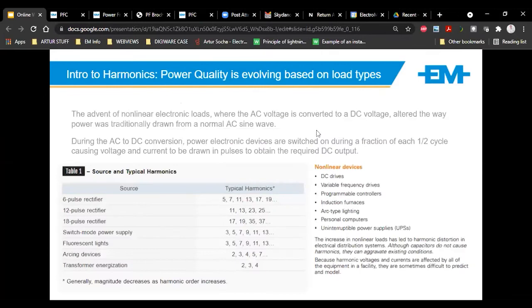So what creates these harmonics? Our loads have evolved. Before we had direct on lines, then we went star deltas, then we went variable speed drives. So VSDs, switch mode power supplies, computers, arc-type lighting, almost anything that's converting AC to DC will affect the power and create a bit of a harmonic. Depending on how it's switching, it will affect different harmonic orders within your network.